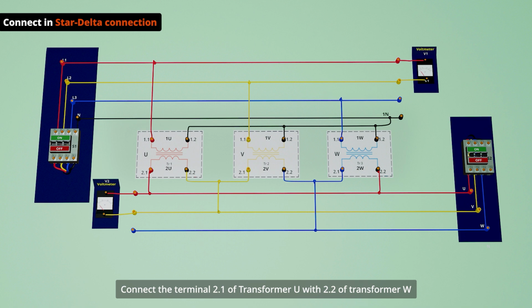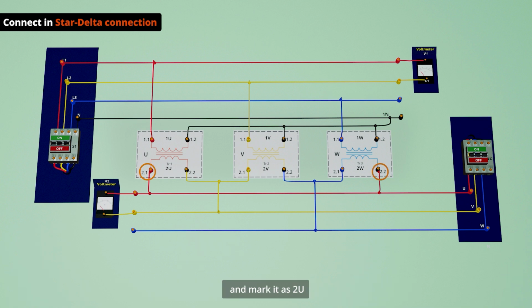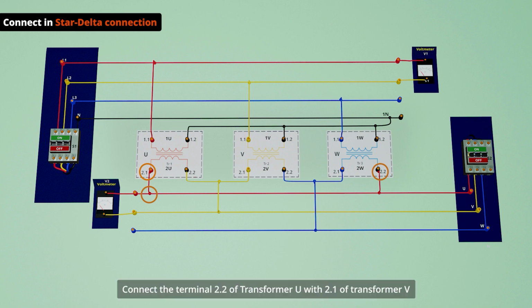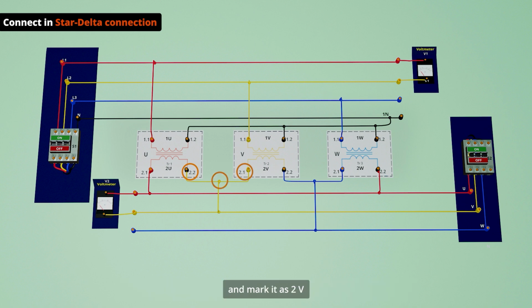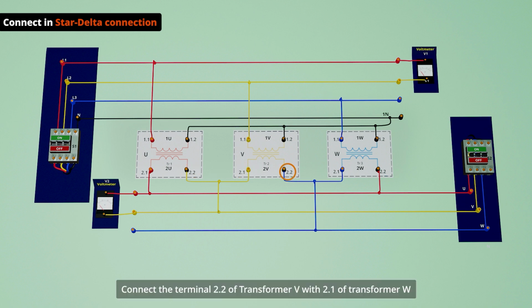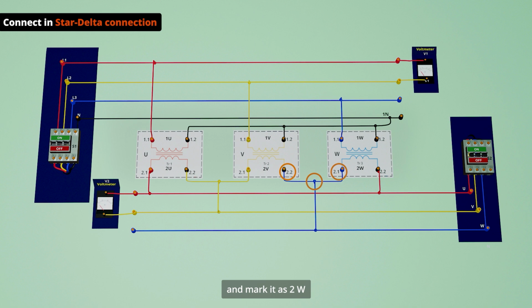Connect the terminal 2.1 of transformer U with 2.2 of transformer W and mark it as 2U. Connect the terminal 2.2 of transformer U with 2.1 of transformer V and mark it as 2V. Connect the terminal 2.2 of transformer V with 2.1 of transformer W and mark it as 2W.